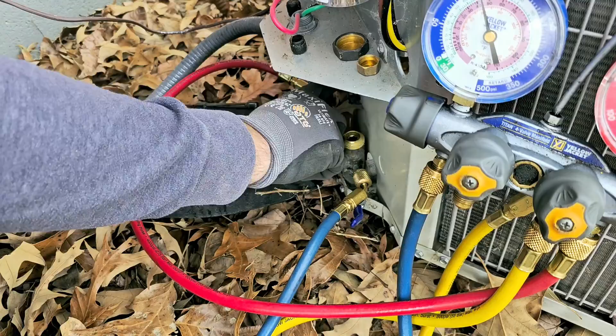All right, so how are we going to do this? We're going to use our service valve wrench, right? We're going to close our liquid line service valve. It's going to be pretty easy. Going to do this right here. Close it down. Why are we doing this? Because the refrigerant flows from the vapor line here into the system, and then it goes into the compressor, out of the discharge line, into the condenser, and then out through the liquid line. So whenever we close the liquid line, the compressor is going to pull all that refrigerant, or pump all that refrigerant, into the unit. Now, I can't use this for this one, okay?